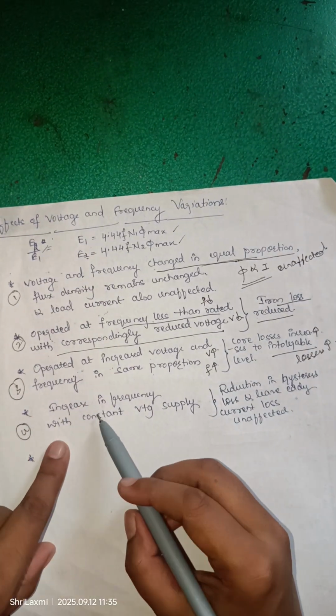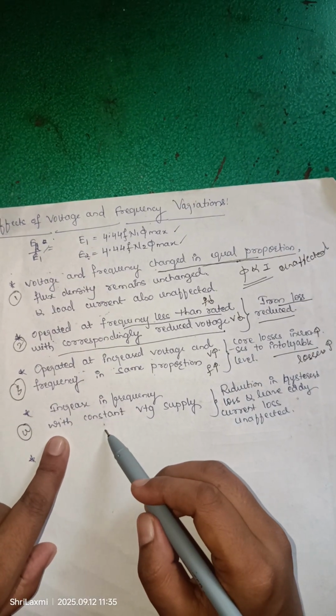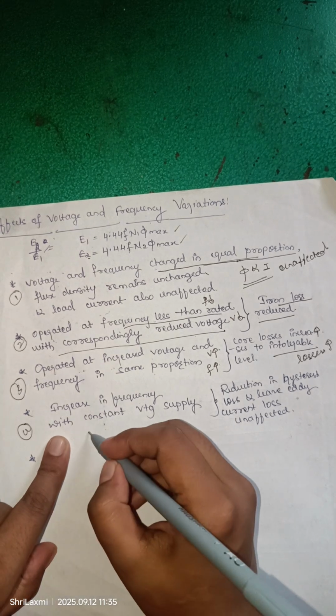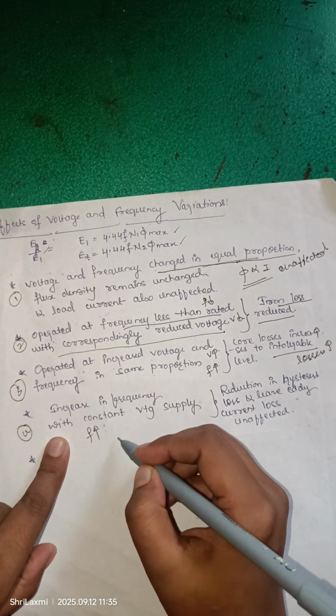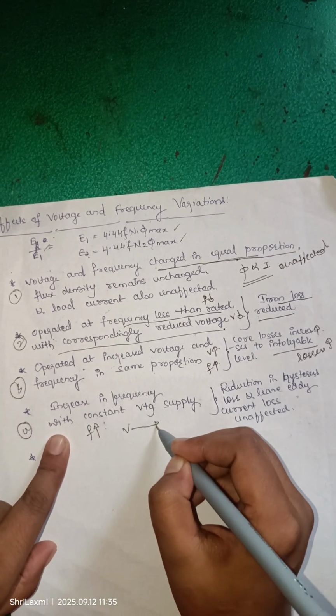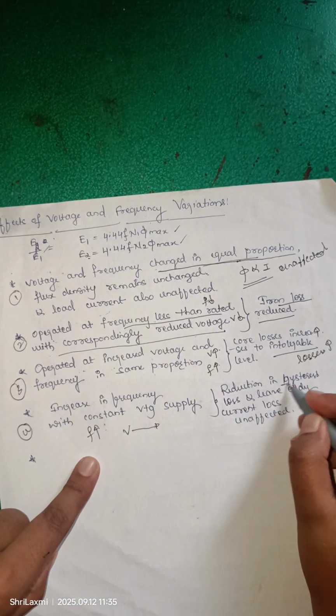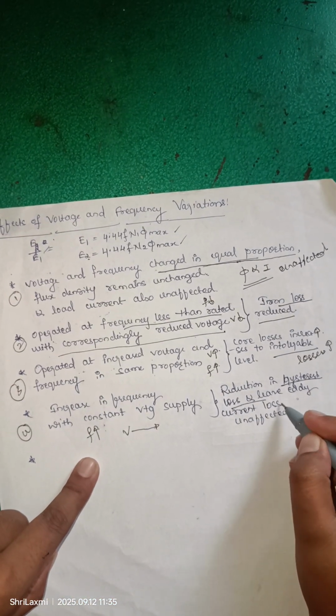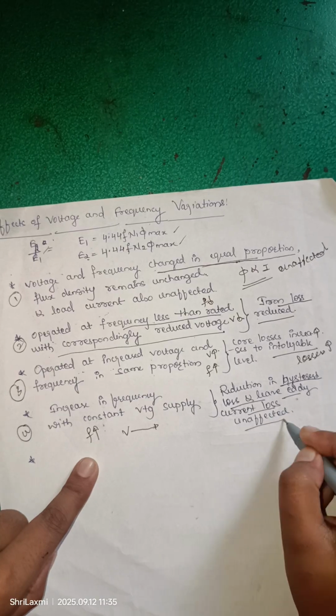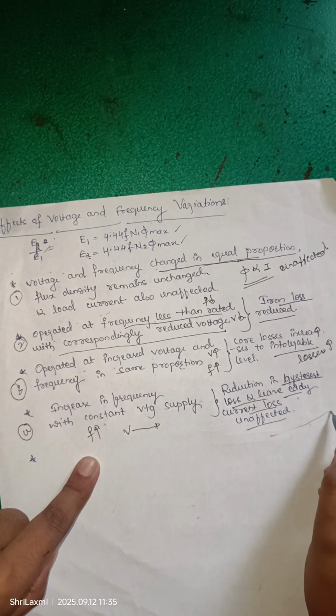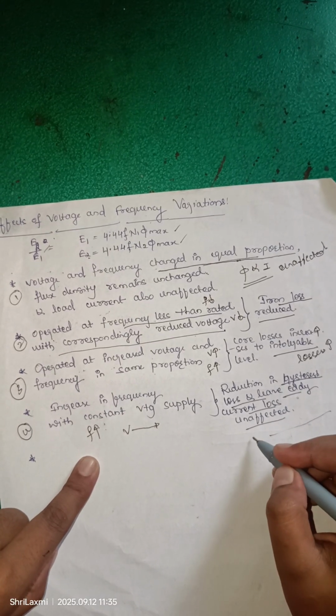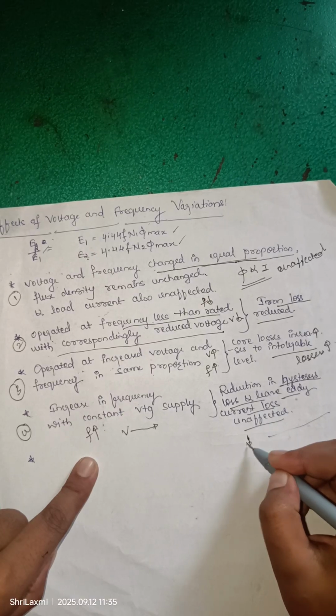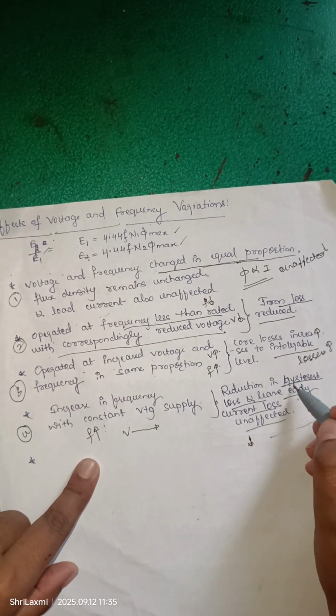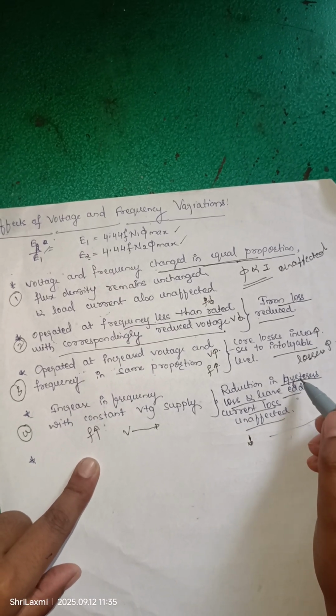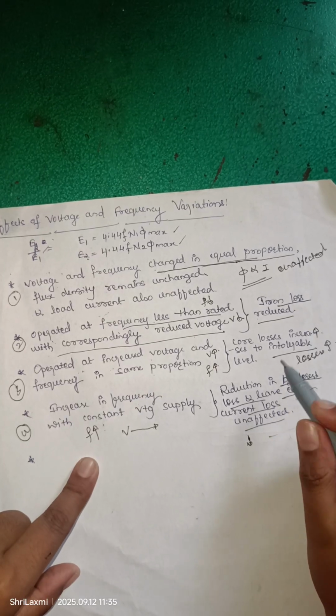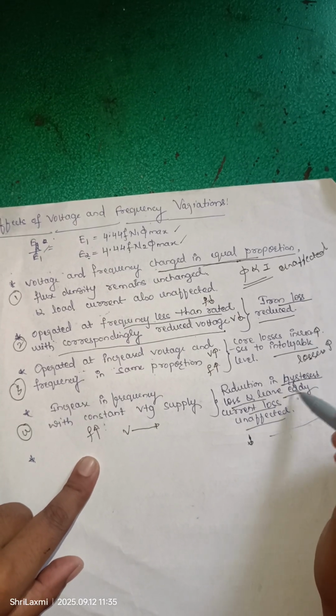Next, if we increase the frequency with constant voltage supply, keeping voltage constant, there is a reduction in hysteresis loss, leaving eddy current losses unaffected. Eddy current losses remain the same while hysteresis loss gets reduced. In the losses section I will explain all these losses: iron loss, hysteresis loss, and eddy current losses.